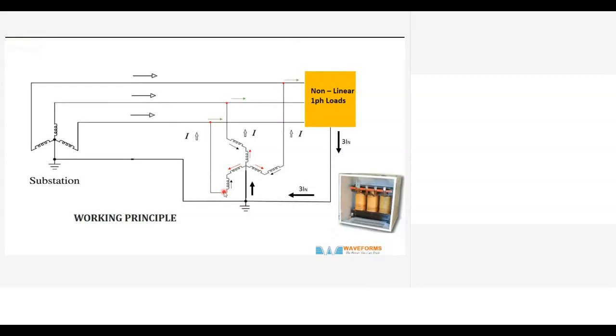So both ways you can reduce the third harmonics circulating in the computer center, because the third harmonics, if not filtered, will circulate inside the UPS. It can increase the temperature. So you can reduce the heat inside it by about 23%. So the air conditioning will work less also. So you can improve the efficiency of the data center substantially.